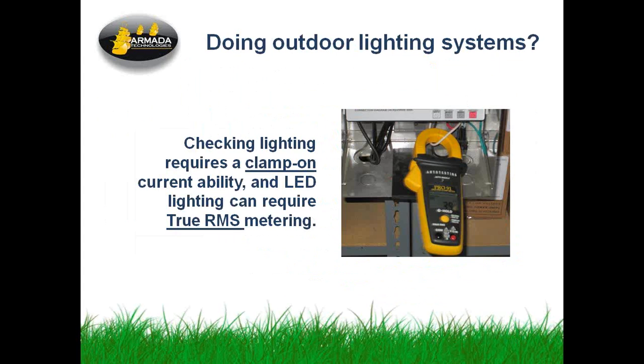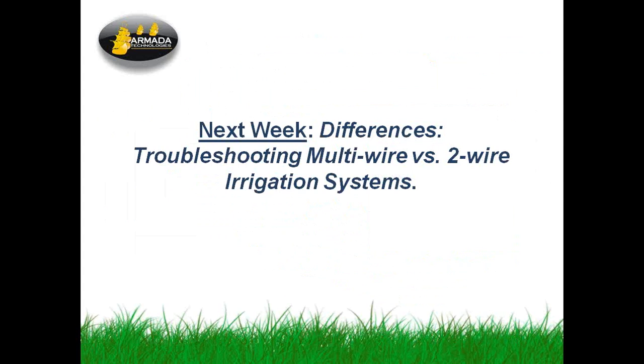So here's an example of using the Pro91 in a lighting system. If you've got an LED system, we've chosen a Pro91 here because it's true RMS, and clamped around one of the output leads going to the field string, and measuring, allowing the current to sit. It takes a little bit. The computing meter settles down after a few seconds. You clamp it on and let it sit for a little bit and get a final reading, and that is the true power. So you can take 12 volts, if you use your voltmeter, check to see how much voltage there is, typically around 12 or 13 volts, and then the amount of current you read on the screen there, and multiply the two together, and that's the true wattage that's being provided to the field. Big benefit of the true RMS meter is you can do that simple math, and it'll tell you what the real watts are being delivered. An averaging meter will tell you a low number. It'll tell you less watts than you're actually consuming in the field.